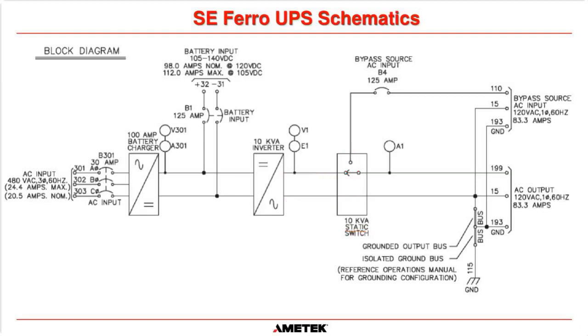Now, the UPS is programmed to choose the inverter at all times, unless something happens to the inverter output. And then if something happens to the inverter output, then the system will transfer over to bypass automatically, and the bypass will supply the load circuits here, because our loads are out here on cable 199 and 15. Okay, now, yes, a lot of people are going to say, well, wait a minute, this is drawn as a switch. In truth, I don't know why we do that, and I don't think it's the best thing to do. It can be drawn much better than this using the actual symbol for a static switch, which is back-to-back SCRs, but we choose to draw it as a switch. So don't get confused. This is not a mechanical switch, although it looks like it. This is a static switch.